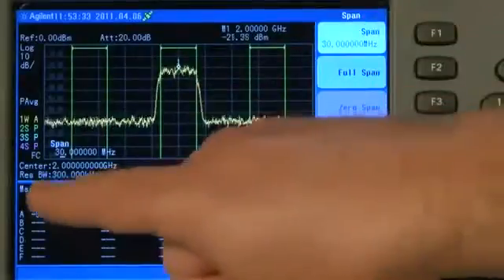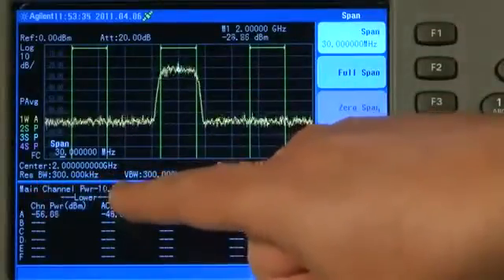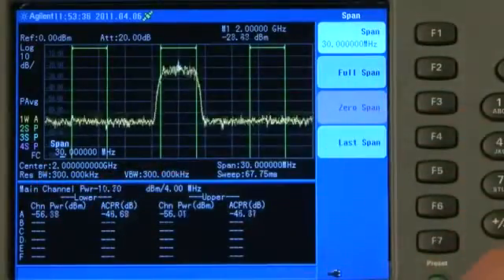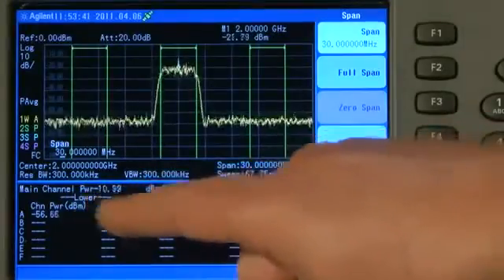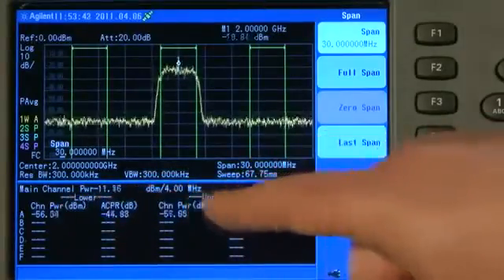So, as well as measuring the power in the main channel here, it says main channel power about minus 11 dBm. We are also, in the table below, measuring the adjacent channel power for both the lower and upper adjacent channels.